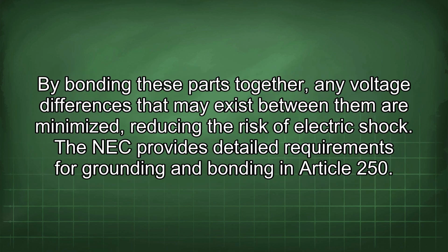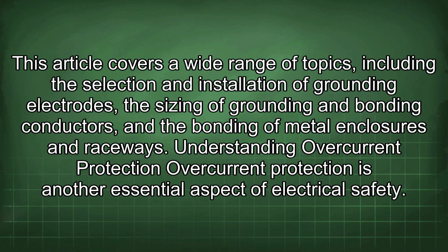By bonding these parts together, any voltage differences that may exist between them are minimized, reducing the risk of electric shock. The NEC provides detailed requirements for grounding and bonding in Article 250. This article covers a wide range of topics, including the selection and installation of grounding electrodes, the sizing of grounding and bonding conductors, and the bonding of metal enclosures and raceways.